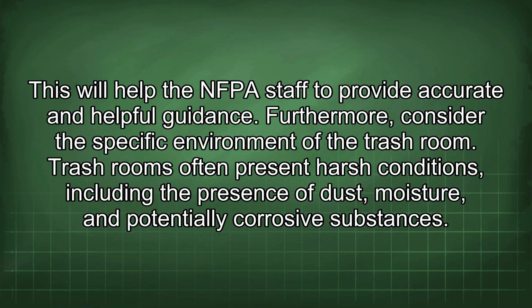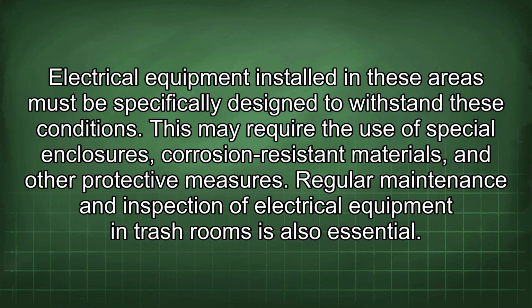Consider the specific environment of the trash room. Trash rooms often present harsh conditions, including dust, moisture, and potentially corrosive substances. Electrical equipment installed in these areas must be specifically designed to withstand these conditions, which may require special enclosures, corrosion-resistant materials, and other protective measures.